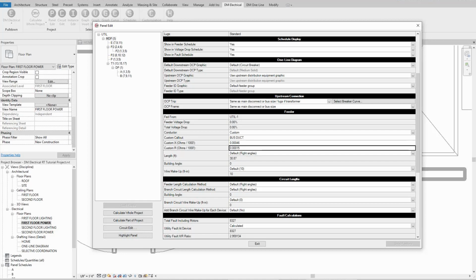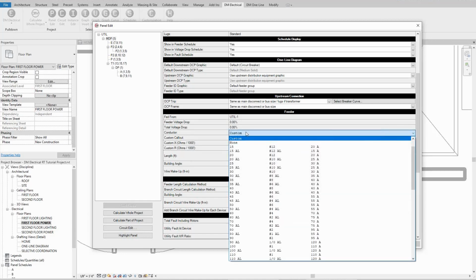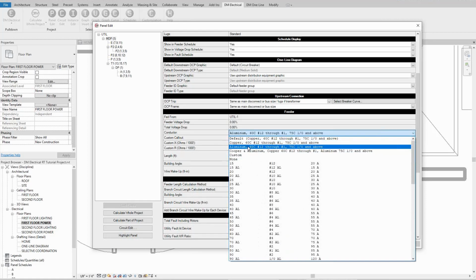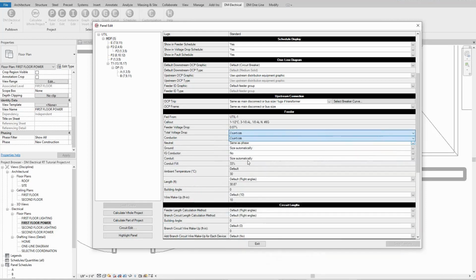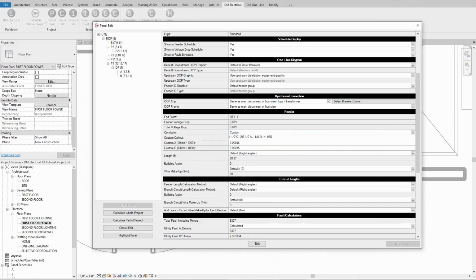But if you want to put them all in one conduit, you can come in here, give us the custom callout as you want to describe it, and then give us the corresponding impedance values. So we could come in here and do custom. Say we want to have 2 runs. Whatever description you want to put in there, you can. And then obviously you'd upsize or adjust the impedance values. And then reset that back to the default.